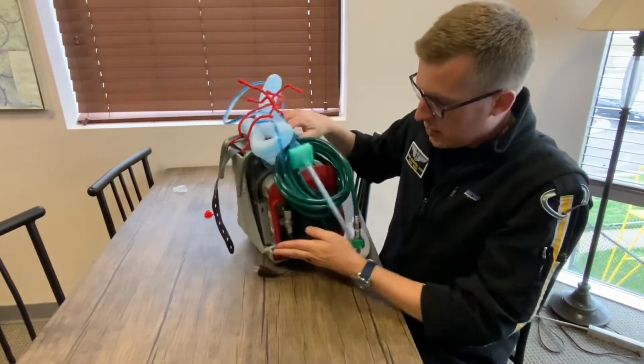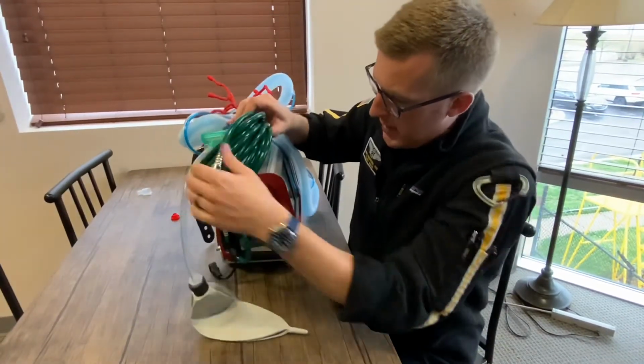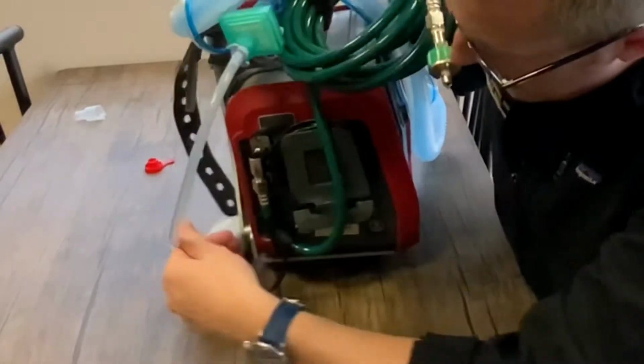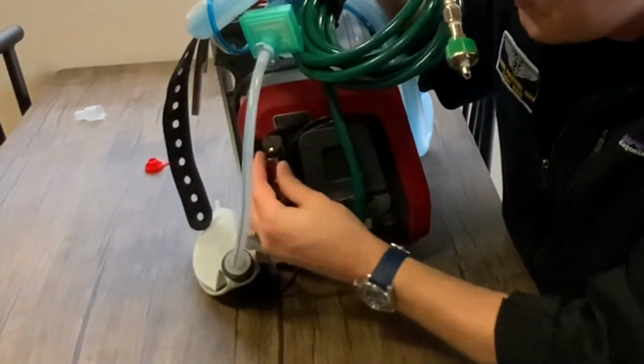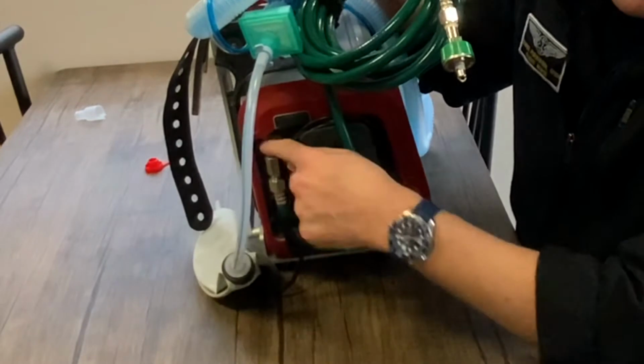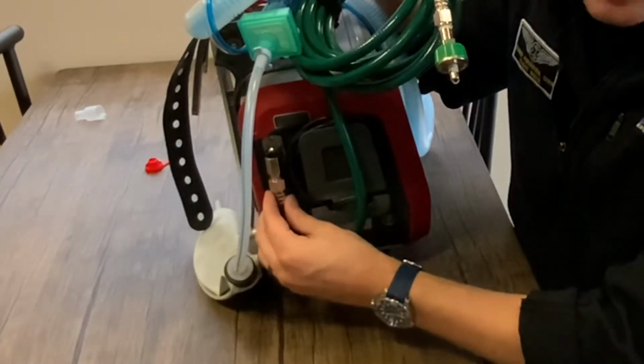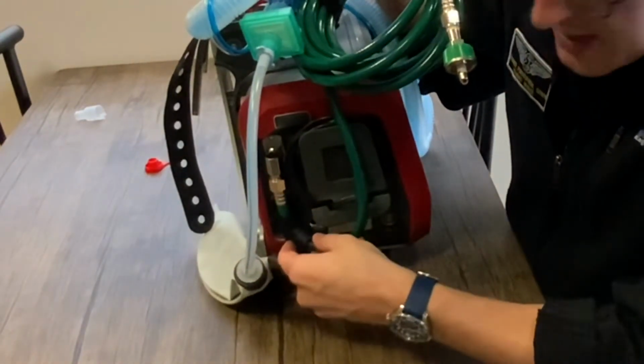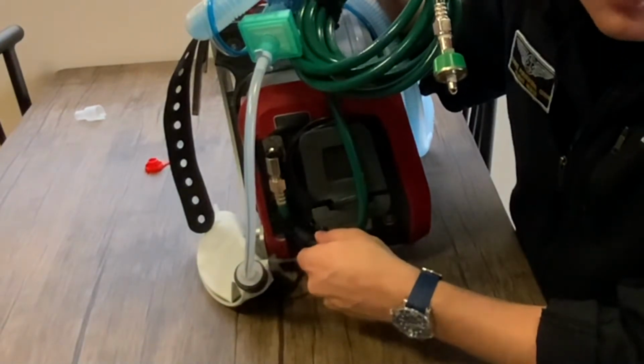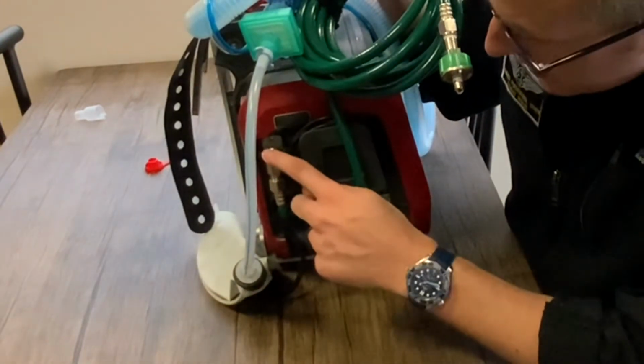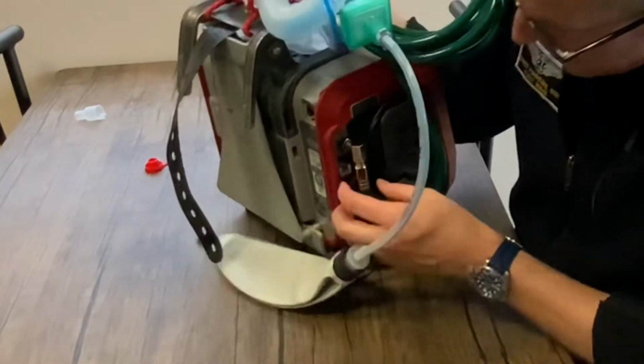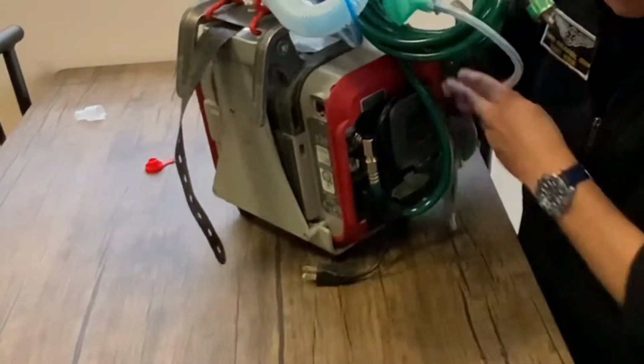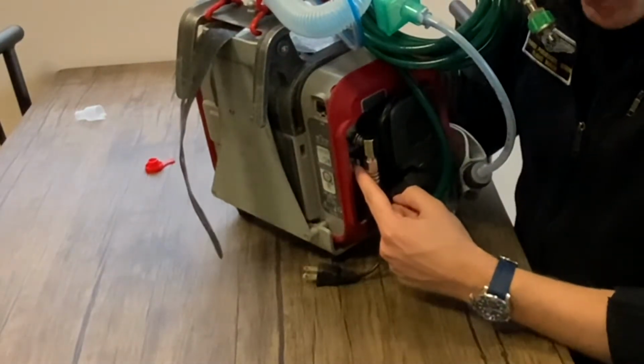When turning the vent all the way around, we have our high pressure oxygen hookup. We have installed a 90-degree elbow to make it a little more ergonomic and to not have the high pressure oxygen cable shooting straight out. I highly recommend the 90-degree elbow. Below that, we have the low pressure oxygen hookup, which we will not be using.